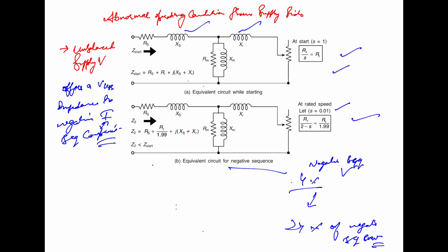Because in that case the slip is small, that is 0.01, and for the negative sequence we have RR divided by (2 minus S). However, during the starting we have the rotor resistance equal to RR divided by S, and S is 1 in that case. So for a negative sequence voltage of 4%, we will have 24% of negative sequence current as observed, which is drawn by the motor.